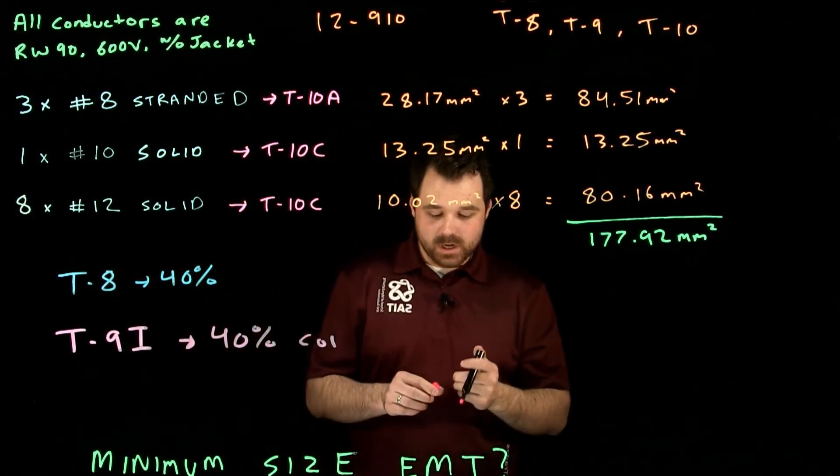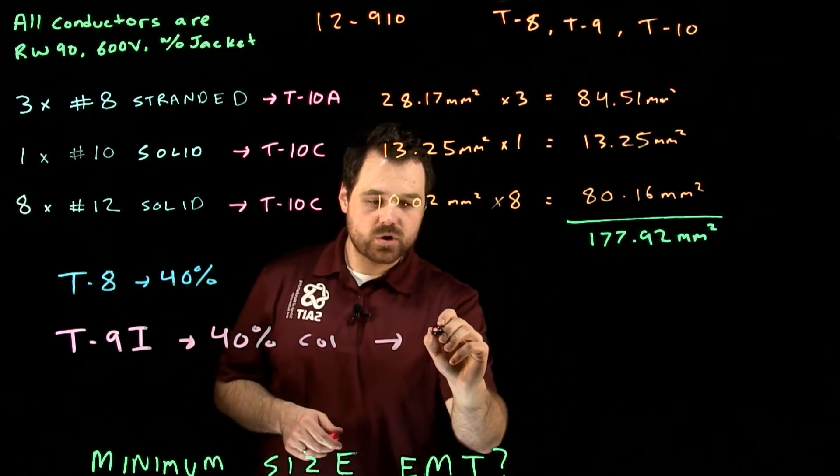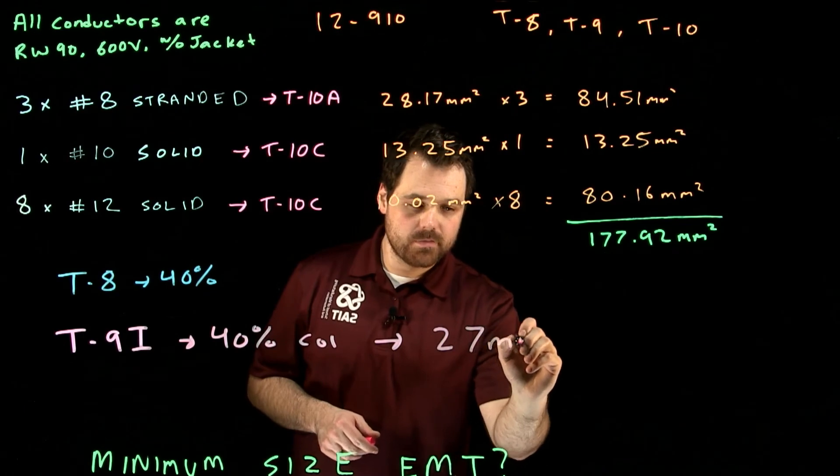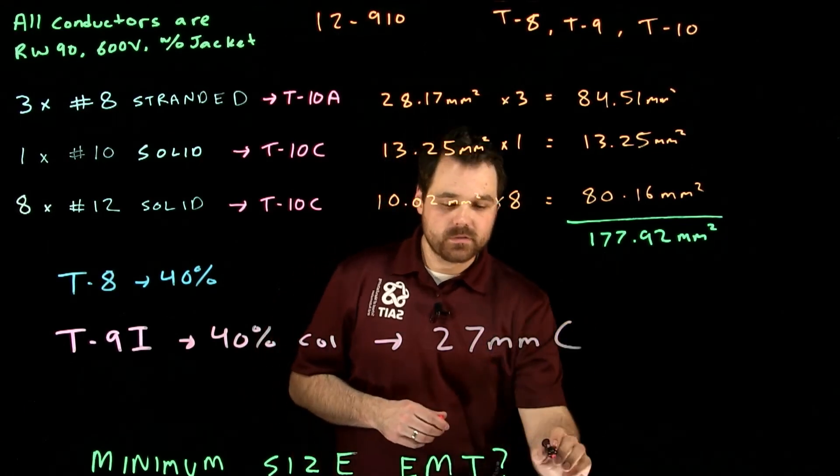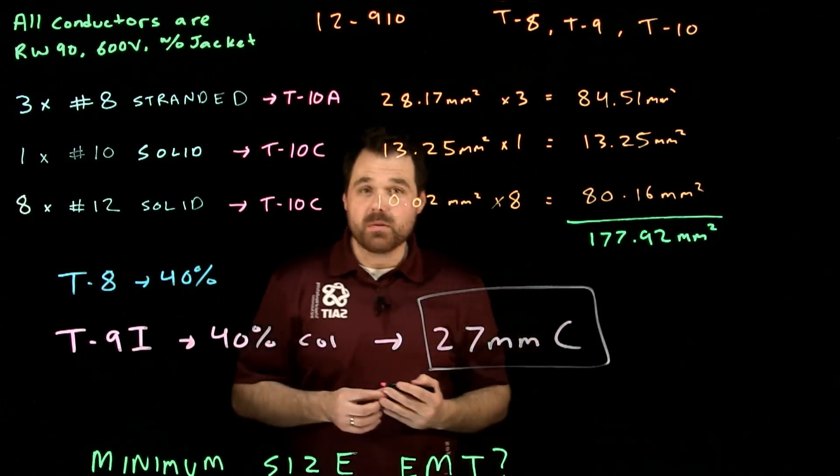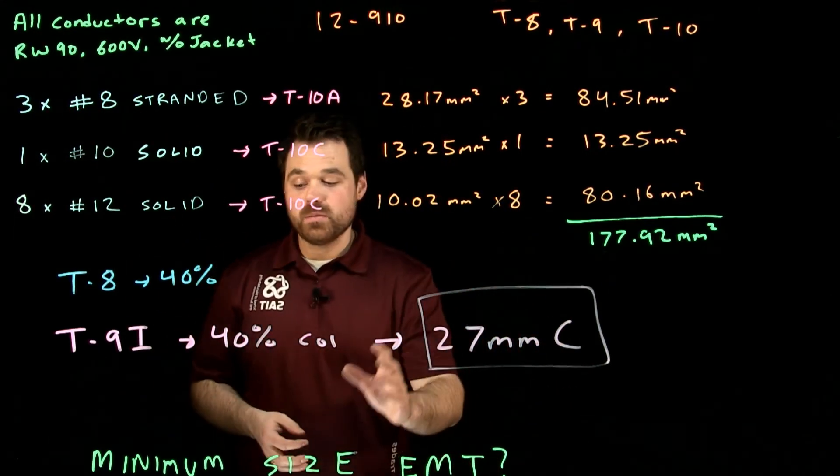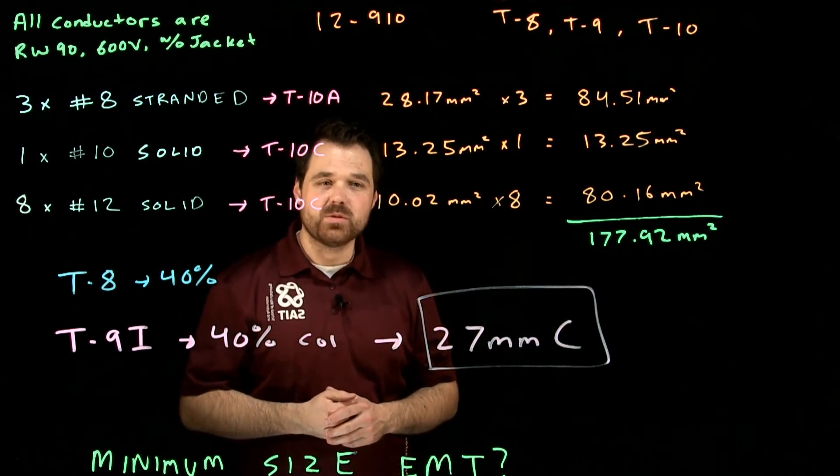And the 40% column tells us that we are going to need a 27 millimeter conduit. So a 27 millimeter conduit is the smallest conduit by code that we could use to pull in these conductors. And that conduit would be an EMT or electrical metallic tubing.